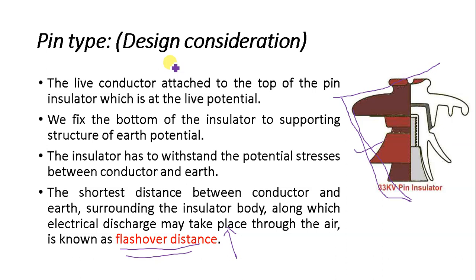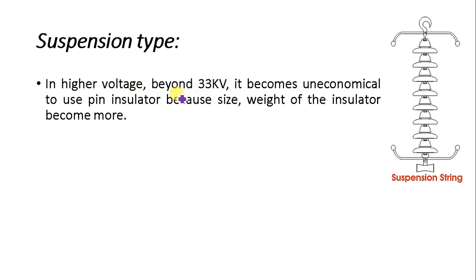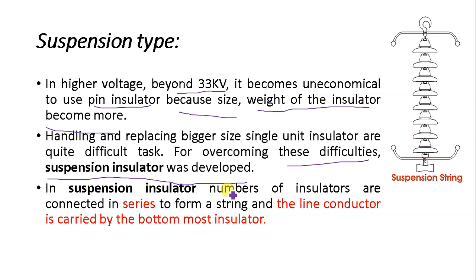Now let us discuss the suspension type insulator. For voltages beyond 33 kV it is uneconomical to use pin type insulators because the size and weight become large, making handling and replacement difficult. To overcome these difficulties, suspension type insulators were developed. In a suspension type insulator, a number of insulator discs are connected in series to form a string.